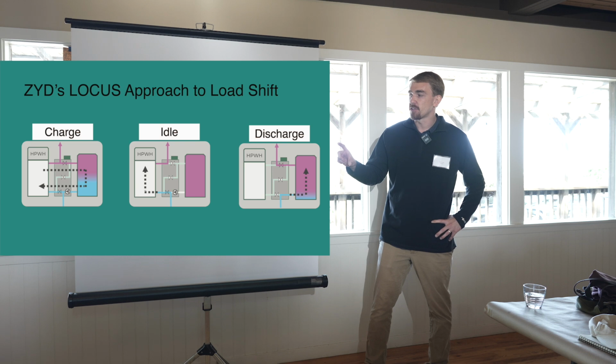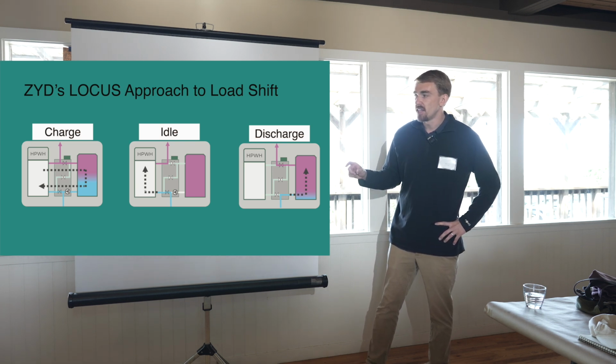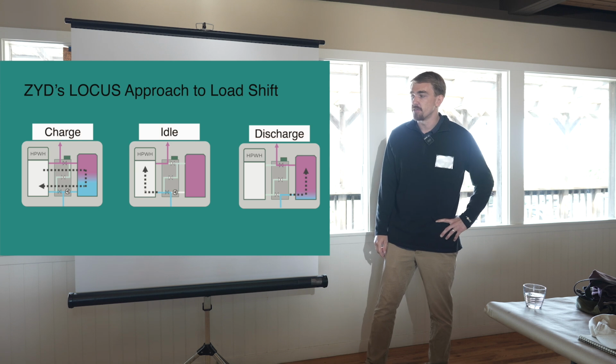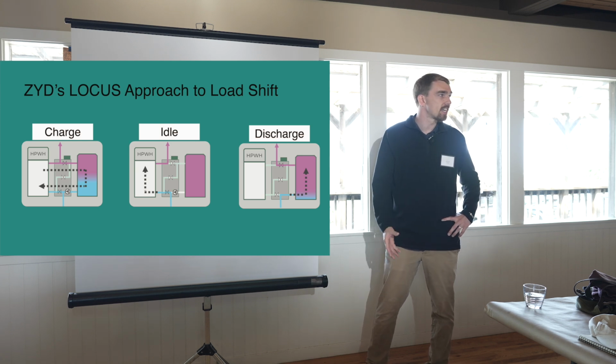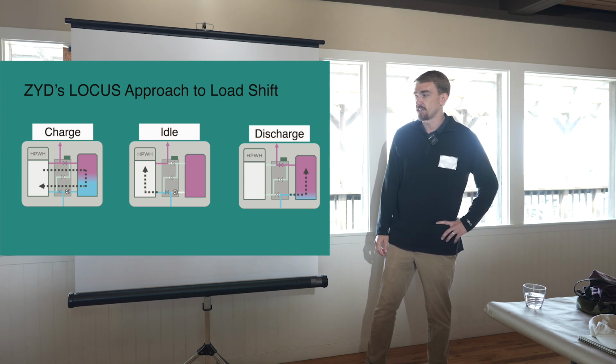After that storage is charged, we'll put it in idle mode, or ZYD will, and we have a fully hot storage tank ready to be used during that peak load during the shed period, and the heat pump will handle the load on its own. So it'll see the draw just as it would if it didn't have the controller attached.